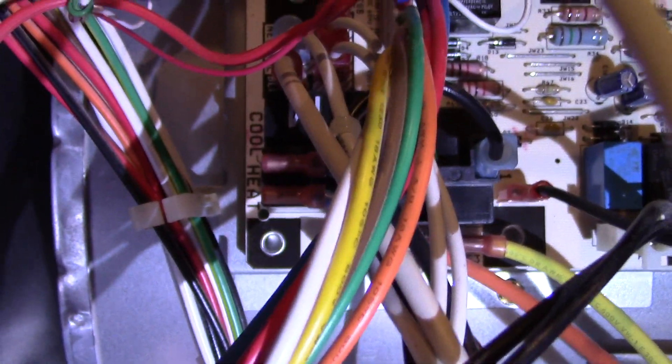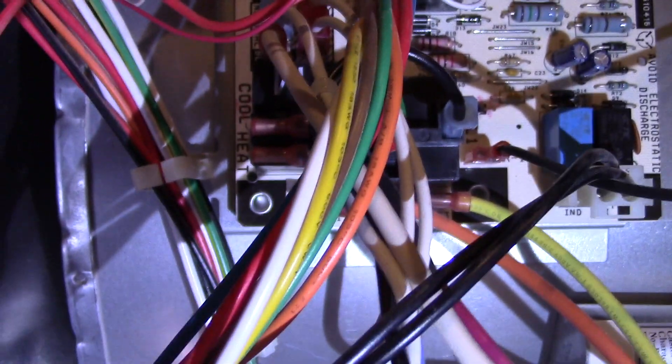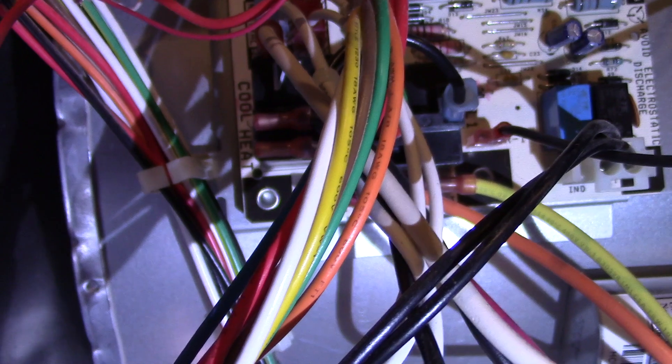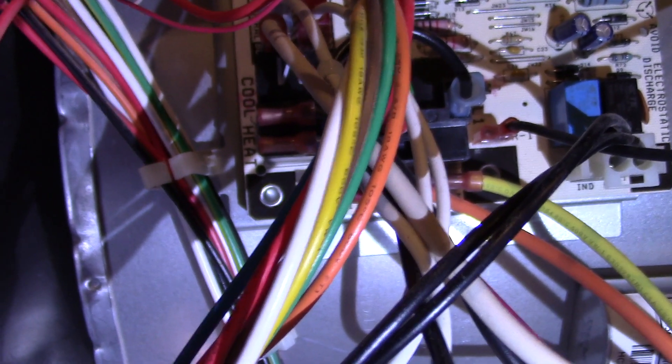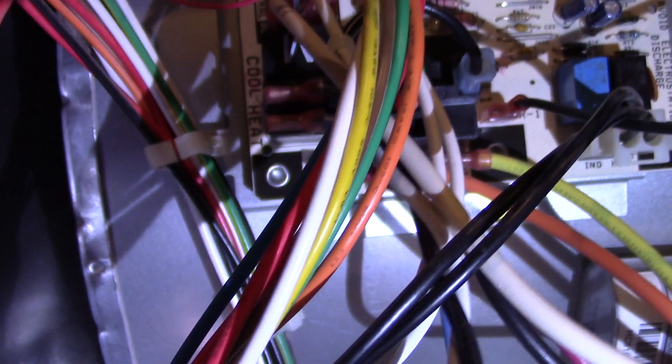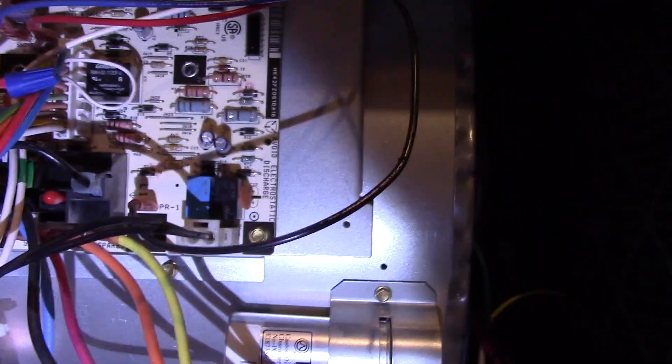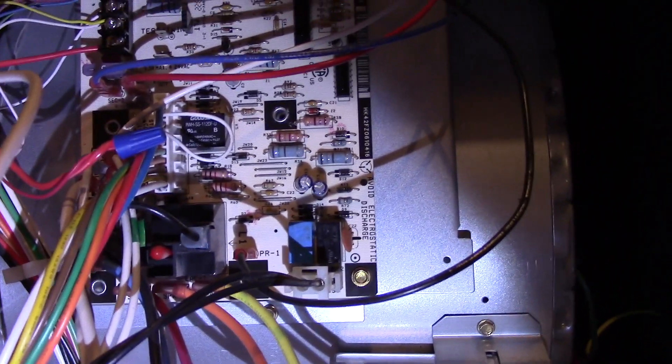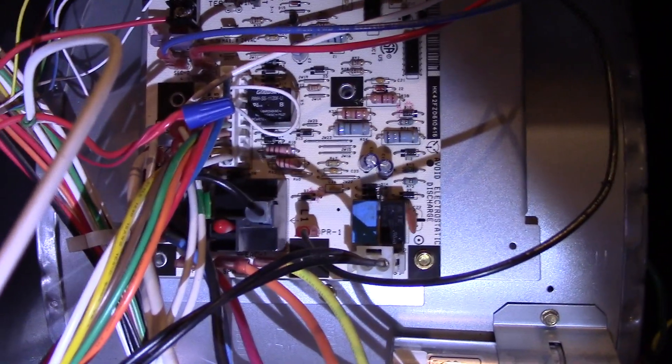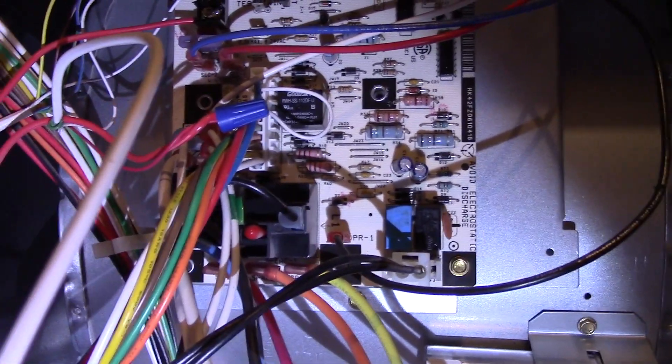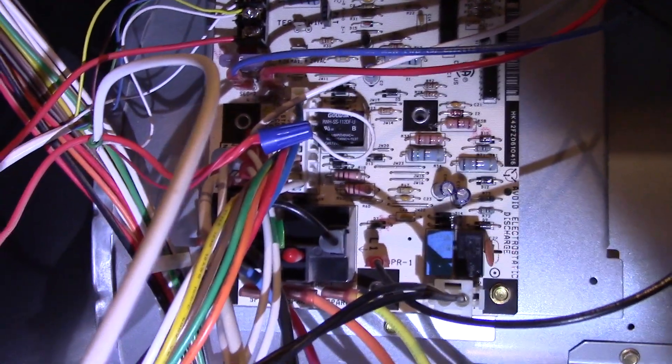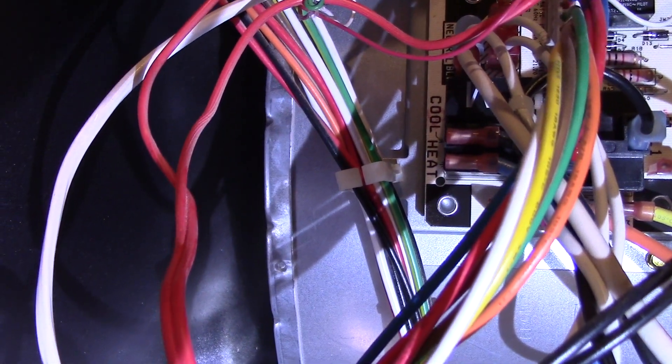Now, this particular furnace is a single stage, which means there's just one speed for cooling, one speed for heat. It's on or it's off, basically. If you have a two-stage furnace, you'll probably have a high heat speed and a low heat speed. If you have one of those variable-stage furnaces or variable-speed blowers called the ECM motor, well, first of all, you have my sympathy. Second of all, that's beyond the scope of my knowledge, so I'm not going to describe how to adjust those. I'm just going to focus on the PSC motor.